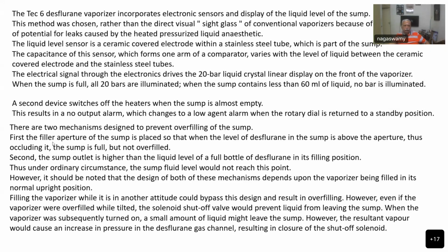Whereas here, the first is that the filler aperture of the sump is placed so that when the level of desflurane in the sump is above the aperture, thus occluding it, the sump is full but not overfull. So the filler aperture, as I showed in the picture in the earlier class, when the level is above the aperture, it will get filled but it will not get overfilled.